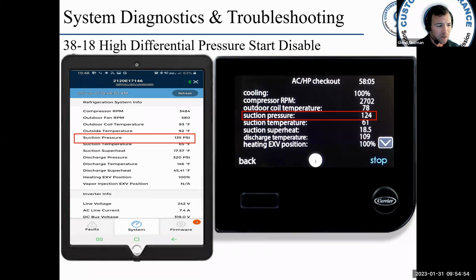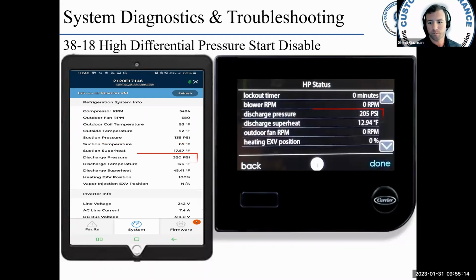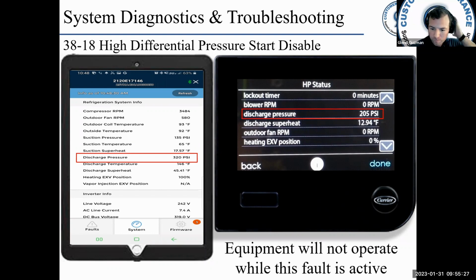What it's going to try to do is open the pressure equalizing valve. It's going to try and open the valve for 10 minutes. If the valve continues not to reduce the differential, then you're going to get the high pressure differential start disable. Okay. Again, looking at the app, looking at the UI and comparing it to your gauges will be critical to troubleshooting this fault. Okay. The equipment's not going to operate while this fault is active.